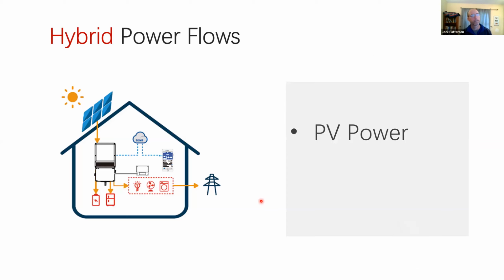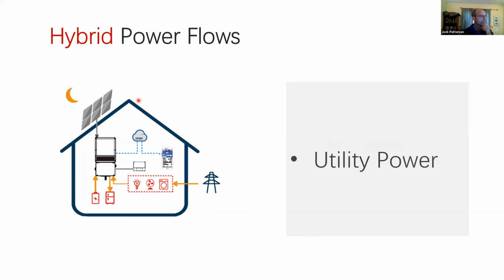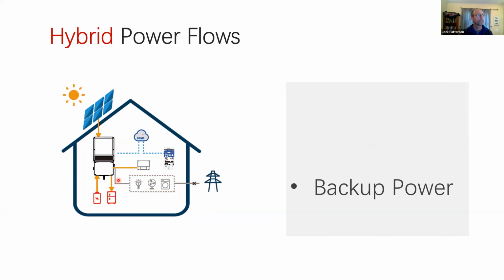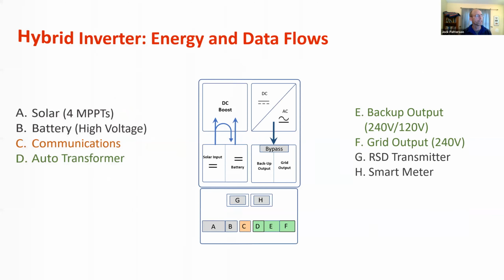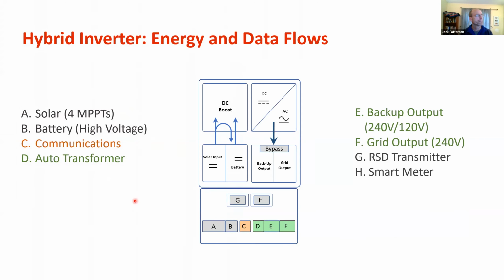So what happens in the hybrid? Well, the sun is out, you're getting energy coming into the inverter, and it can feed the battery if it needs charging, your essential loads panel, or your main service panel of loads. It could also go out to the grid if there's extra. But now we're at night. What happens? Well, you still can get from the grid, but your battery could supplement, especially if you're in a peak time of use period. So power flows can come into the inverter from these two sources. However, if the grid is out, then it's up to the PV and battery to supply the essential loads. And that's just the different sort of flowing you'll see occurring depending on the operating status.